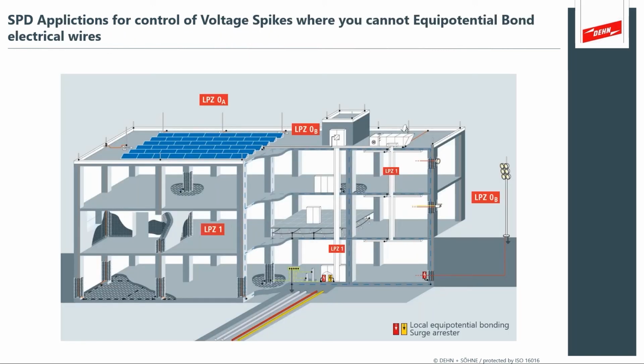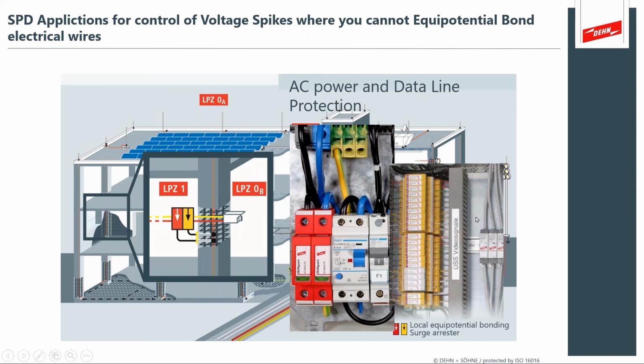So you want to control voltage spikes where you cannot equipotential bond your electrical wires. And that's what we see in this illustration: you're applying surge protection devices throughout the building at critical junctures to adequately control the voltage on your AC power and on your data line. And here we see some illustrations of data circuit protection. Perhaps you've got power over Ethernet cameras throughout your building, and you want to protect that exposed camera and that back door for the voltage to come in and otherwise pollute and cause damage into your system.